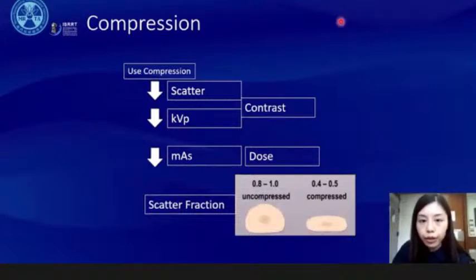Besides the positioning, another technical factor that we can control is compression. Nowadays, it is a basic idea that if we use the compression technique, we can reduce the scatter and kVp, which will lead to a higher contrast of the images. And it can lower the mAs, which will reduce the patient radiation dose. It is reported that the scatter fraction can be reduced by almost 50% after we use the compression technique.